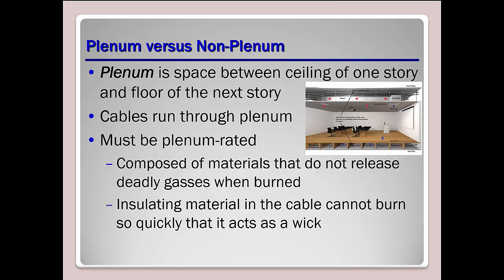Back to plenum versus non-plenum: plenum grade cable is required when running cabling in the plenum space — the area above dropped ceilings — to ensure it won't give off toxic gases in a fire. In networking labs with raised floors, data connections are run up through the floor, and this plenum space is used for things like projector connections.